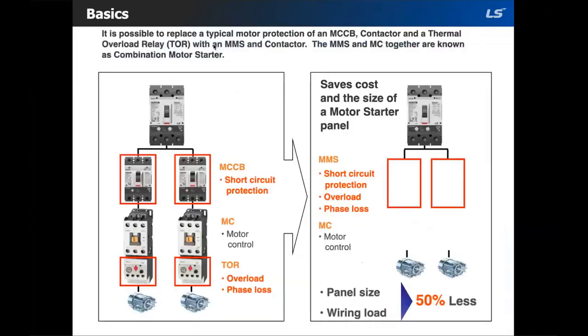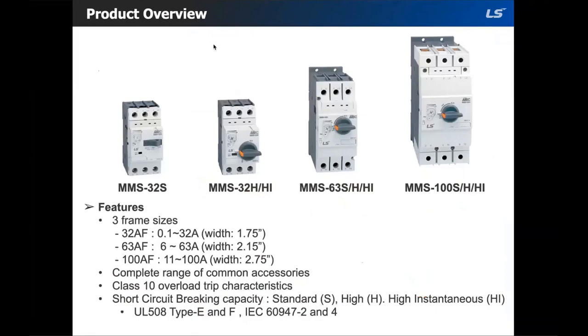So it is also possible to replace a typical motor protection of an MCCB, contactor and overload with an MMS and contactor combination. And this combination is also known as a combination motor starter. In addition to Class 10 adjustable bimetal overload, the MMS also includes a fixed magnetic short circuit trip mechanism designed to trip at 13 times the maximum current rating. As you can see here, we have a standard model which is indicated with an S. H is the higher breaking capacity model, and finally HI would be the high instantaneous model, which only has the magnetic trip at 13 times the max current.